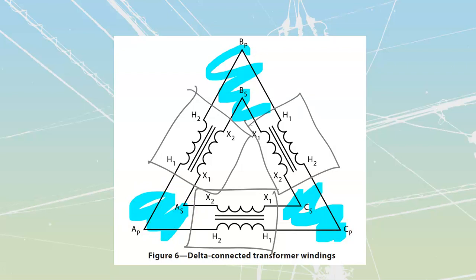Generally speaking, we are not going to do a lot of bank connections unless you're working in really high voltage, high power industries. If you're working for an average commercial or even small industrial setting, you're usually going to buy a single unit that has all three windings already on it, and there are some advantages to buying those three-phase transformers.